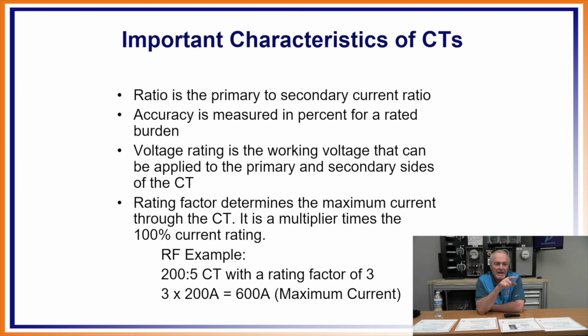As we just said a second ago, we'll use a 200 to 5 example here. So I've got a 200 to 5 CT with a rating factor of 3. Then that means I can actually load up to 600 amps on that CT and it'll still be fine. So as we've said before, I can take a 200 to 5 CT with a rating factor of 3, and I can use it on applications all the way up to 600 amps. So I can use that one CT for a lot of different applications, okay?